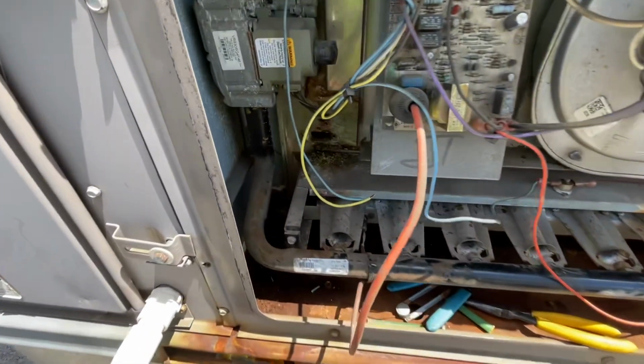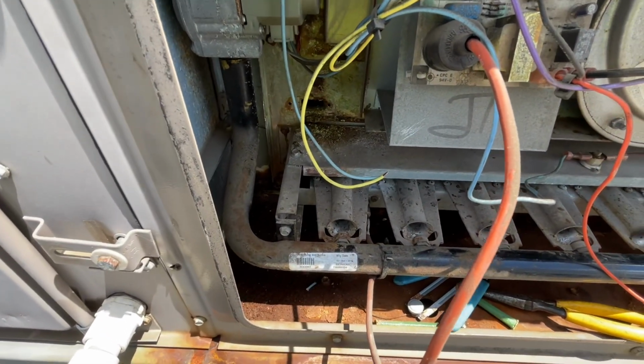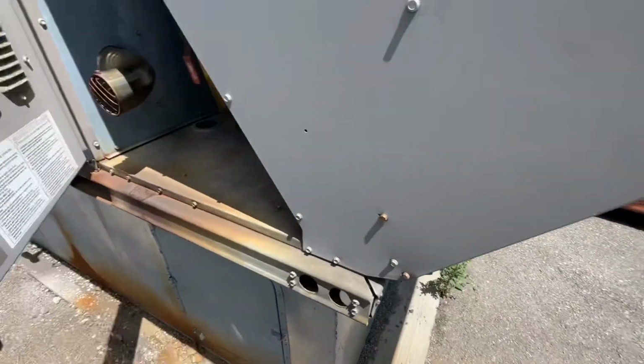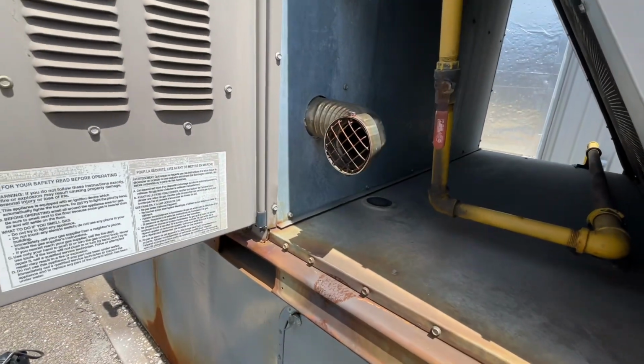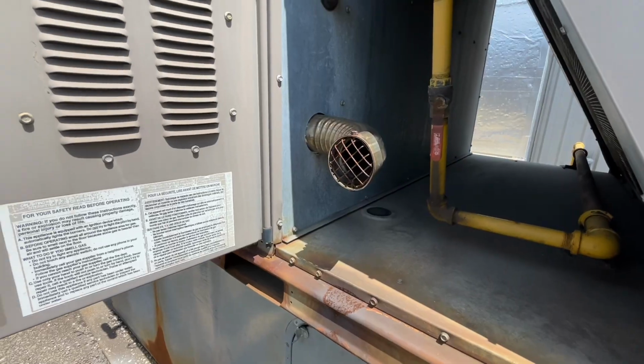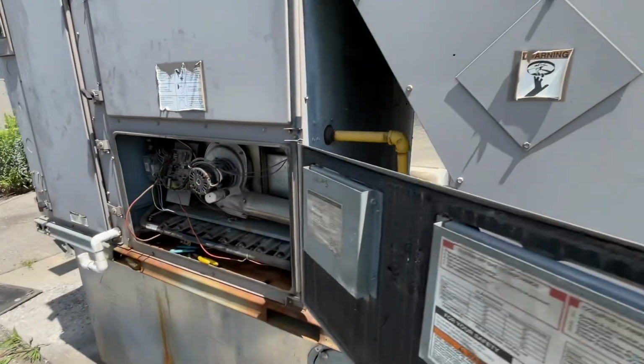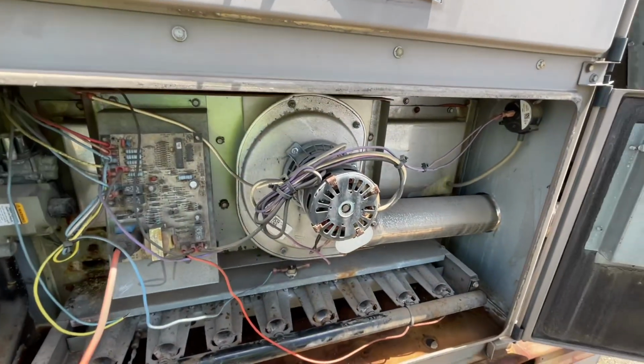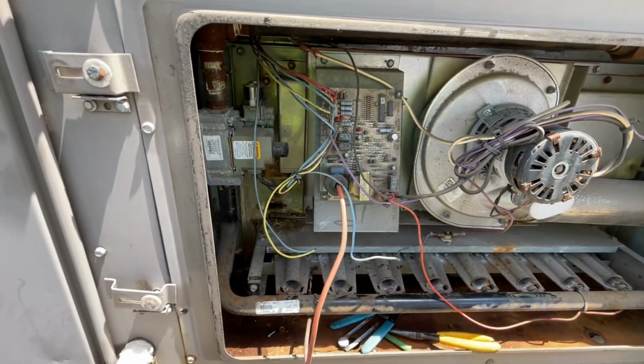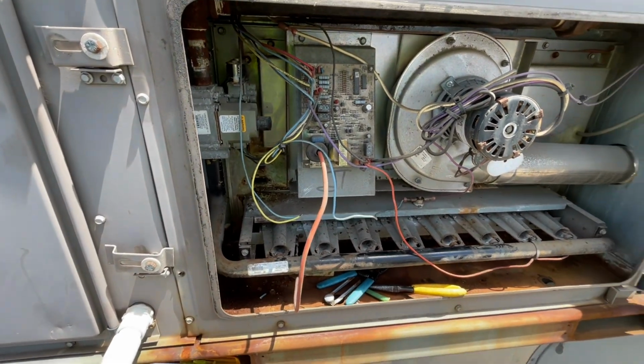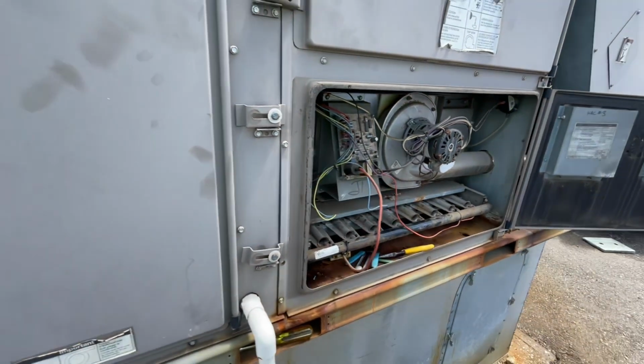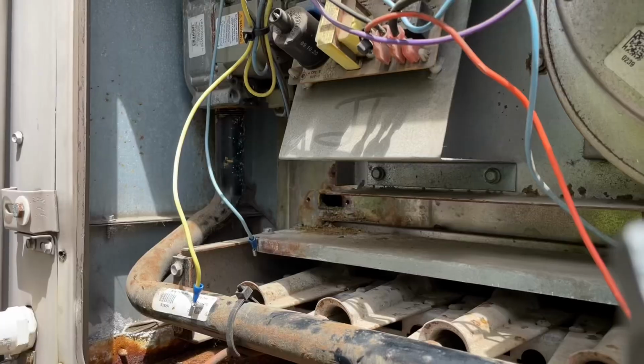That high limit is exactly why our air conditioning wasn't running. Because keep in mind that heating safety will supersede any other control points in this unit. So if we have an issue with the high limit, that inducer will run 24/7, not letting the cooling come on. Let's go see if we can source out a limit and we'll replace it, check our air conditioning.